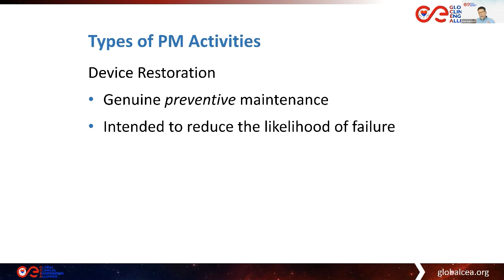It turns out that actually most of the things that we do in PM are more safety and performance verification. It's not exactly preventive. We don't have many things that we need to lubricate, for example, because we deal with electronic devices more than we do with mechanical devices. So a lot of what we do is inspecting for safe and effective function. So we measure electrical safety to make sure the device is safe. We measure the flow rate of the infusion pump to make sure that it's functioning well.